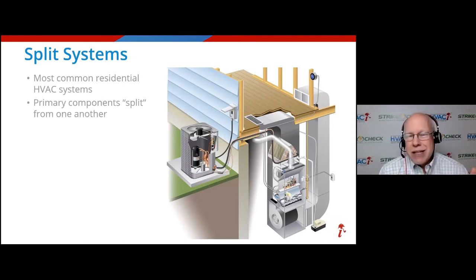They're basically called split systems because the two main components, the condenser and the evaporator, are in two different places. They're split from one another, with that condenser being on the outside of the structure. If it's a small business or a residence, it's usually on a pad next to the building, like in our diagram. If it's a larger commercial building, it's probably up on the roof. And I'll show a picture of that here shortly.